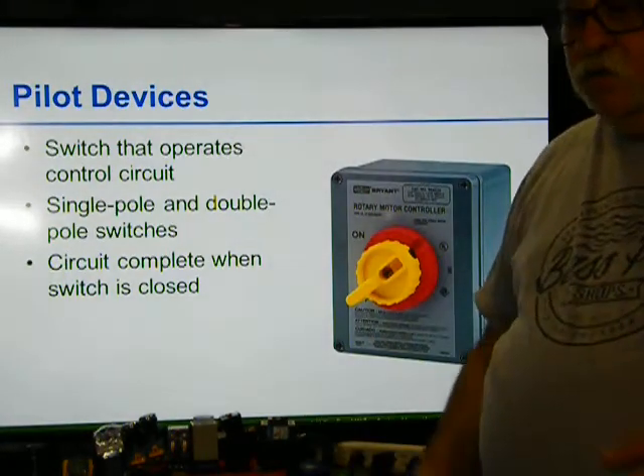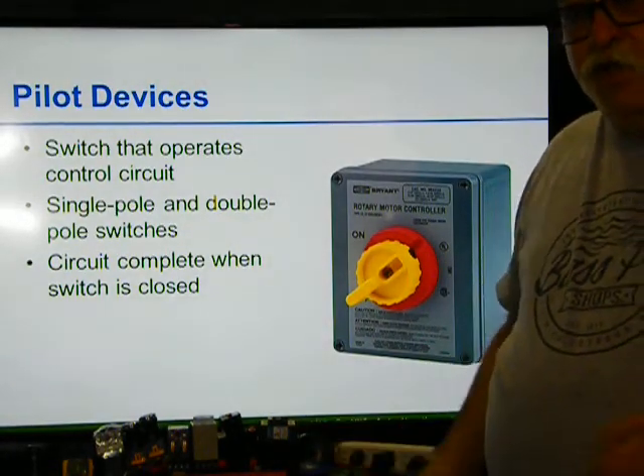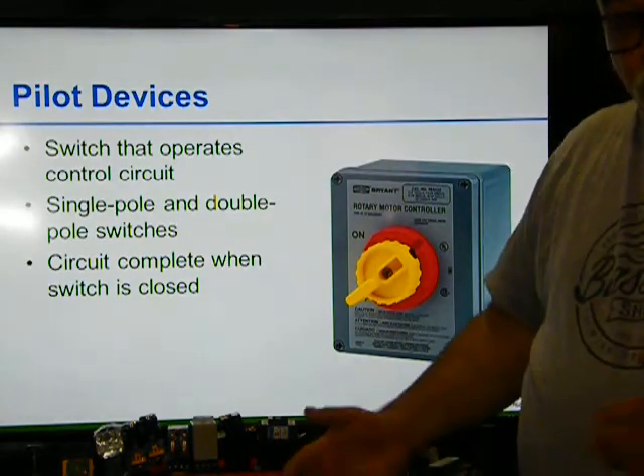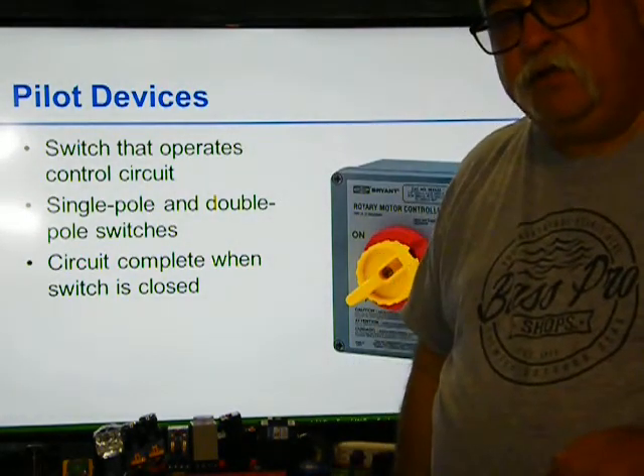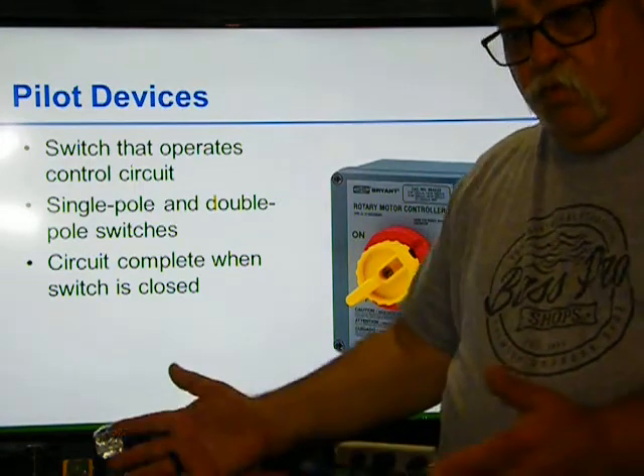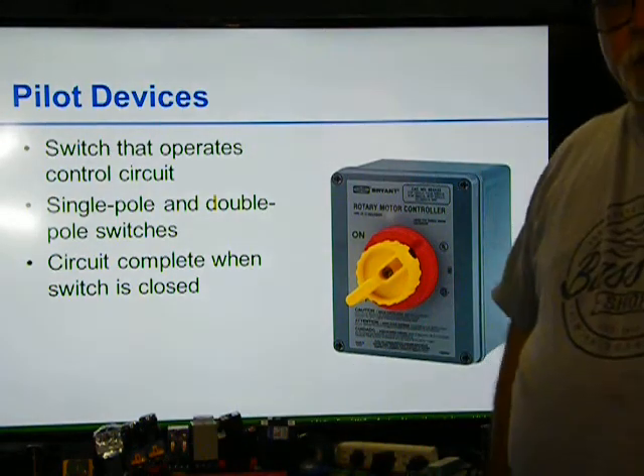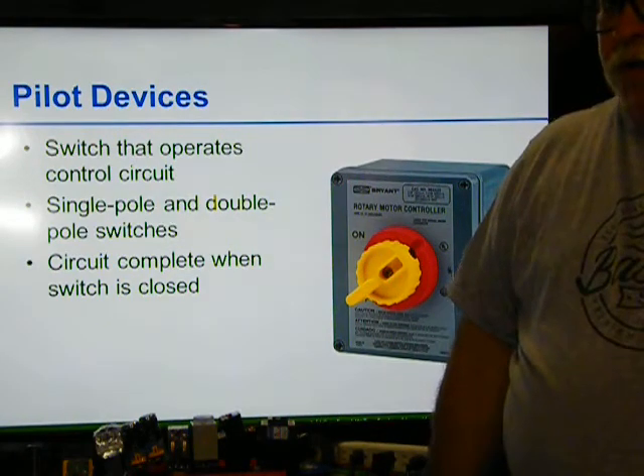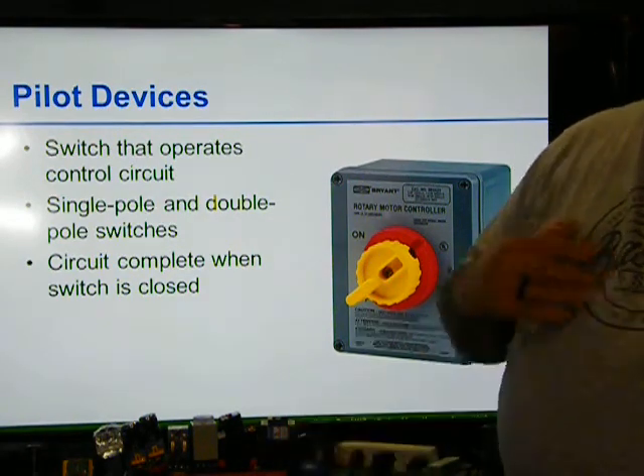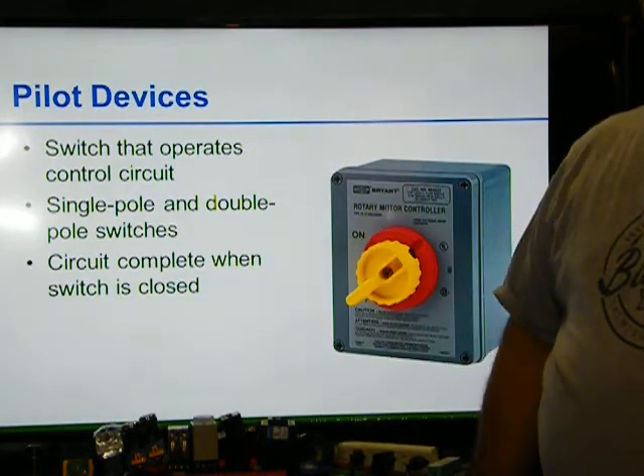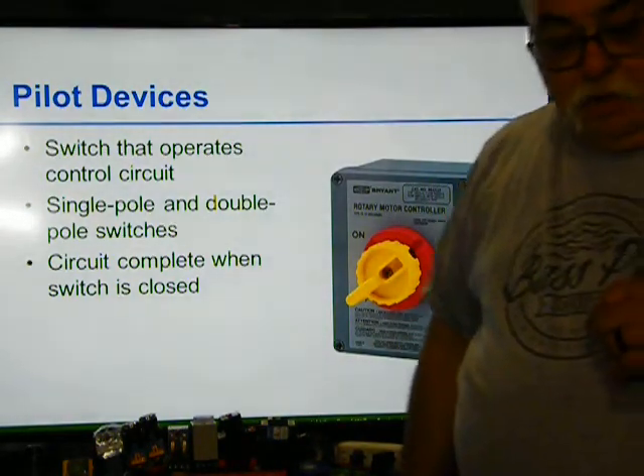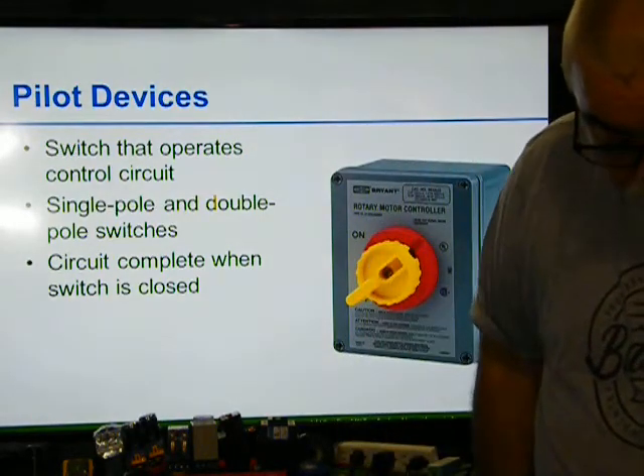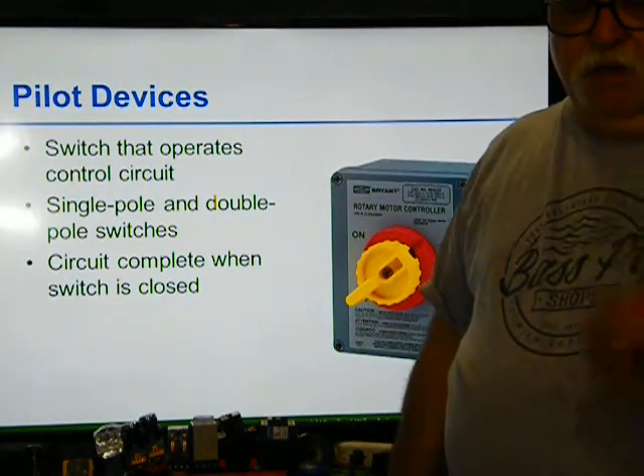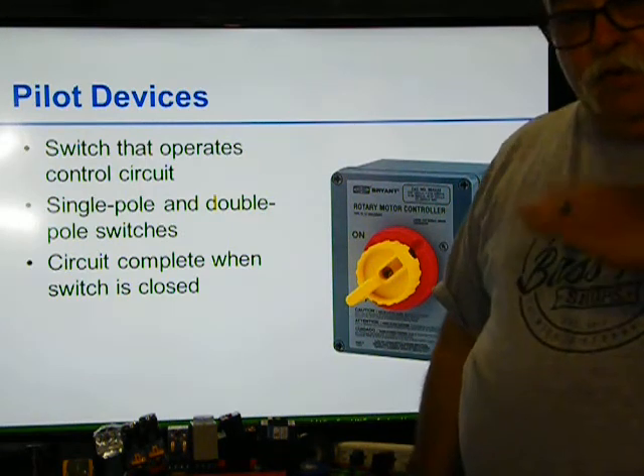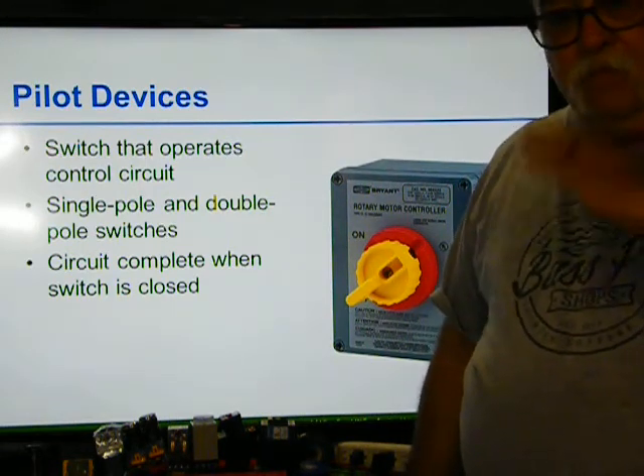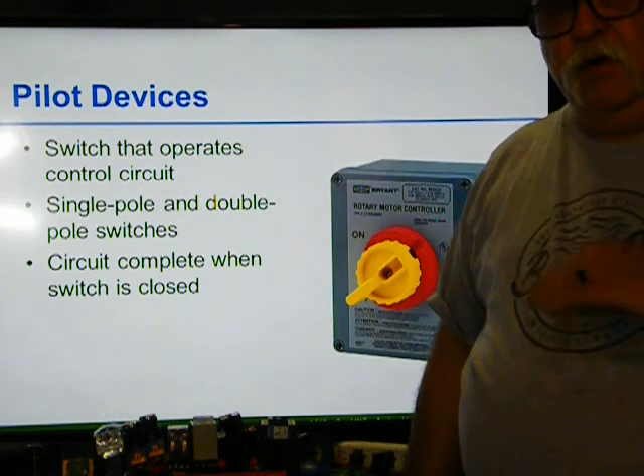Foot switch. We have them on drill presses, on table saws, or any device that you want to have control of. As long as your foot is on the pressure switch, whatever you're working on is working. Once you take your foot off, it stops. It's a safety device: in case something happens and you get hit or knocked down, it doesn't continue to run, because it stops once you relieve pressure off the foot switch. And then a pressure switch is where you have a gas line or a vacuum line, so vacuum or pressure turns it on or off.